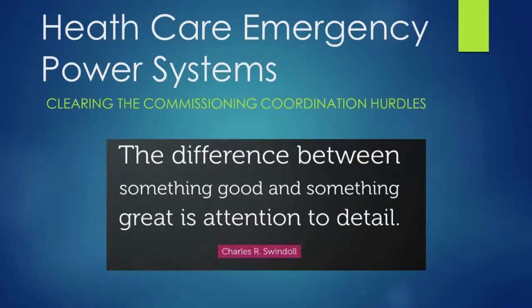If we do need to transfer the load or make a hard transfer, and there's no bypass isolation transfer switch so it just flops back and forth between normal and emergency, then we would coordinate with the departments and equipment affected to minimize impact as much as we possibly could. Your question actually touches on two different tests we normally recommend.